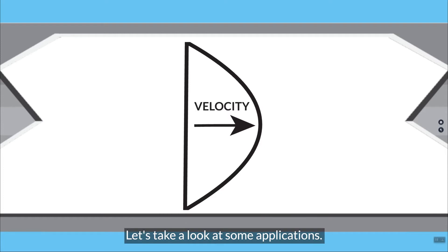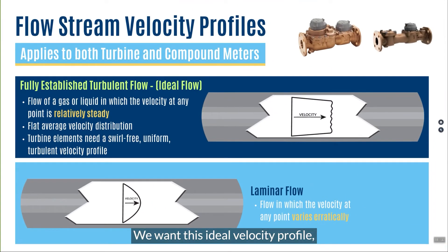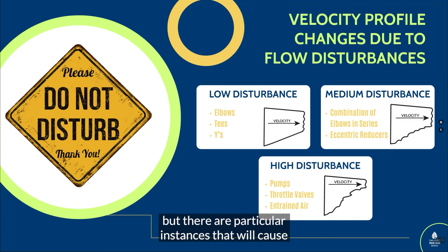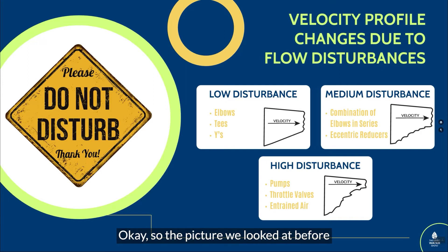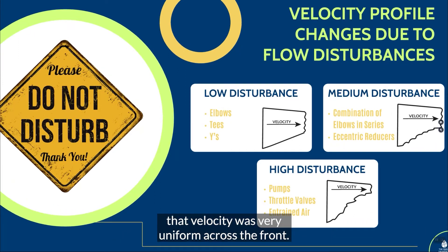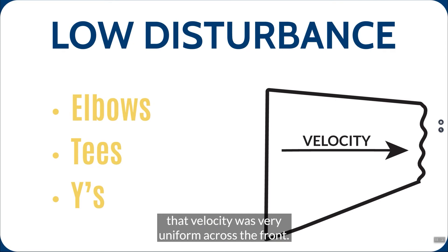Let's take a look at some applications. We want this ideal velocity profile, but there are particular instances that will cause a disturbance to that velocity profile. So the picture we looked at before, that velocity was very uniform across the front. In this case, this is what I would characterize as a low disturbance. Maybe an elbow or a T or a Y in front of the line could cause this skewing of the velocity profile.